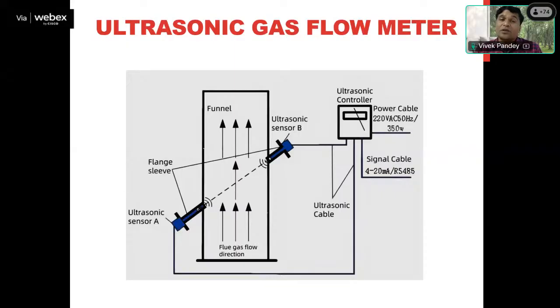And now what will the ultrasonic controller do? After recording that information from sensor B, it will change the operation. Ultrasonic sensor B will now act as a transmitter and sensor A will become the receiver. In this situation, when the ultrasonic wave travels from B to A, it takes more time to reach sensor A. So there is a time gap between the two operations, when the wave transmits from A to B and when it transmits from B to A. Now what is this time gap? It is directly proportional to the flow rate of the gas. The more the flow rate of the gas through the funnel, the more time gap there will be between these two operations.